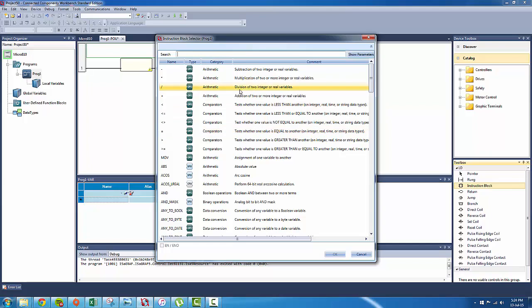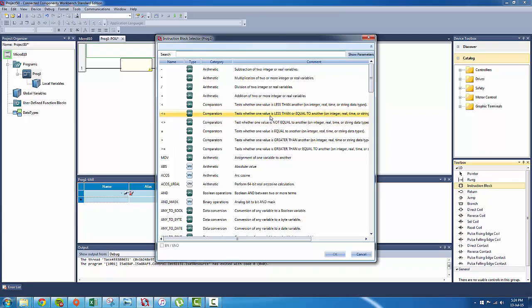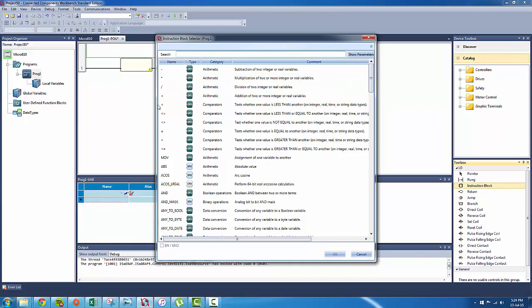Okay, so we've got the less than. So if the value of input one is less than the value of input two, then it's going to energize the output one. That's less than and equals to. The difference between these two is this will only energize if it's lower than. If both the values are the same, so like value one is five, value two is five, it won't energize. Only if input one is less than input two. This one does both. If it's less than or equal to, then it'll energize.